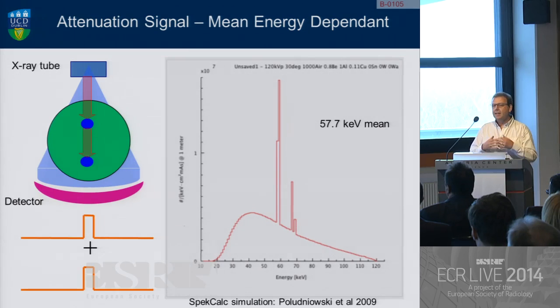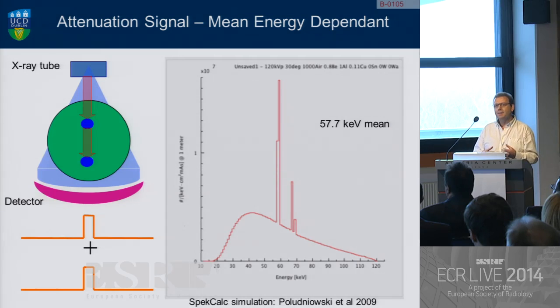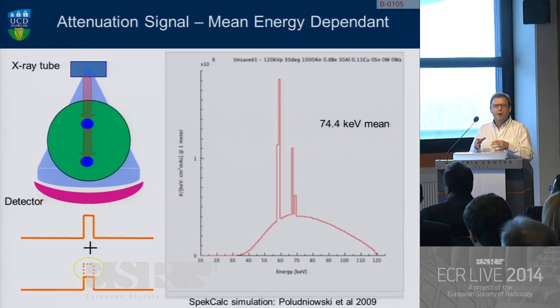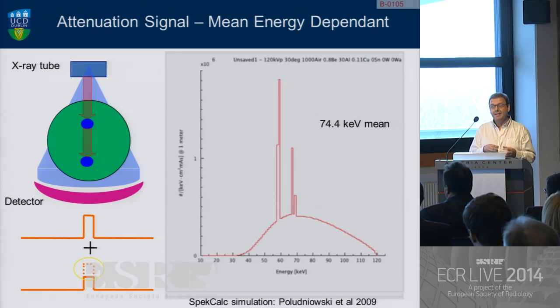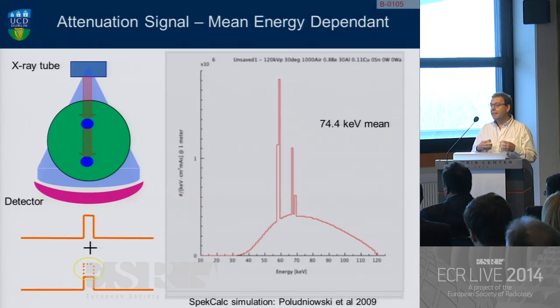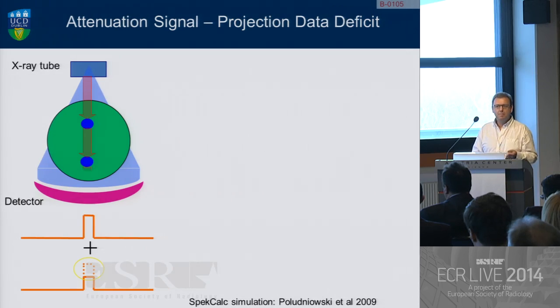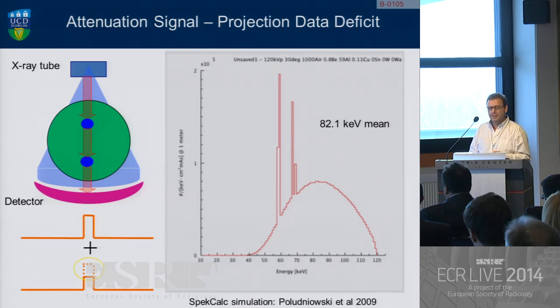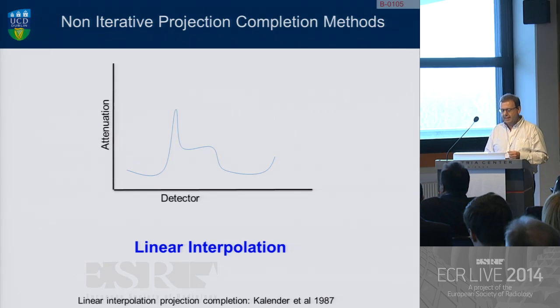If we then put another piece of metal in the beam path, we would like to have the same attenuation signal recorded from that second one. But in passing through the first metal object, what we have is preferential attenuation of the low energy radiation. We see a shift from 57 KEV up to 74.4 KEV by the time the beam hits the second metal object. So we don't have the same energy striking the second metal object, we get a deficit in the recording, and that results in that projection being contaminated. When it passes through the second metal object, the beam energy is shifted even further for any other objects in that path. So we have contaminated projections within the data set.